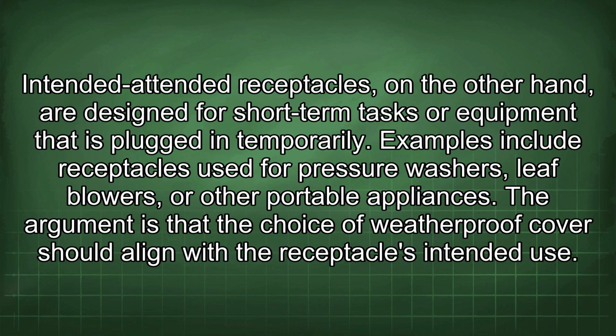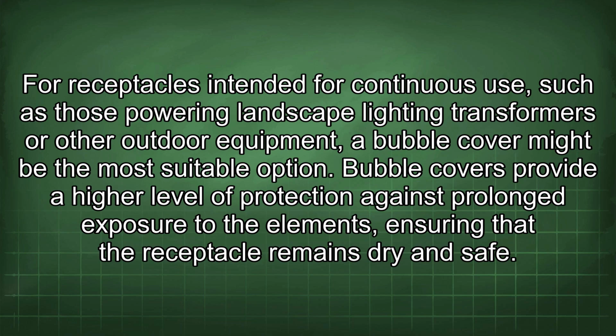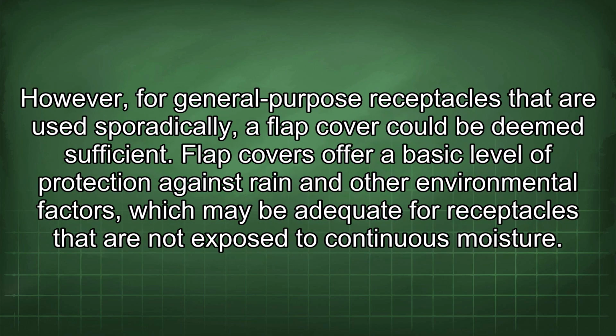Examples include receptacles used for pressure washers, leaf blowers, or other portable appliances. The argument is that the choice of weatherproof cover should align with the receptacle's intended use. For receptacles intended for continuous use, such as those powering landscape lighting, transformers, or other outdoor equipment, a bubble cover might be the most suitable option. Bubble covers provide a higher level of protection against prolonged exposure to the elements, ensuring that the receptacle remains dry and safe. However, for general-purpose receptacles that are used sporadically, a flap cover could be deemed sufficient.